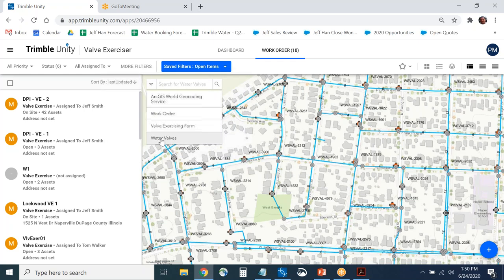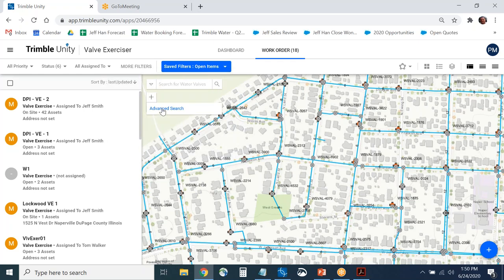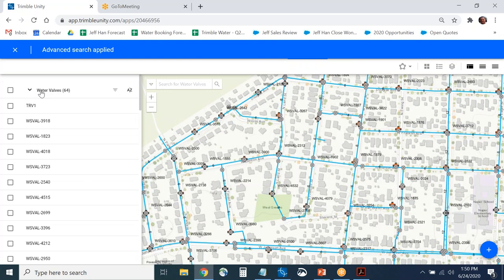For an advanced search, you can do a saved search — for example, looking for water valves where operable equals false. If your GIS has valves marked as inoperable, or any attribute value you're searching for, you can find them with this search tool. Running this query shows 64 records in your GIS where the valve is not operable. You can select each one and create a work order.